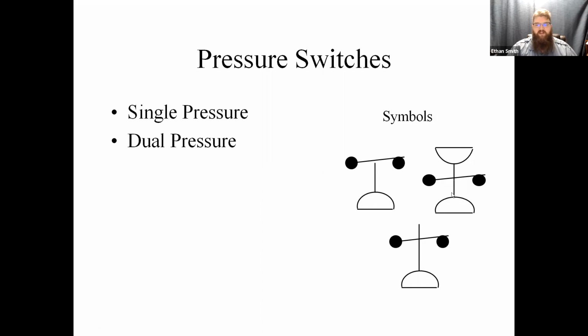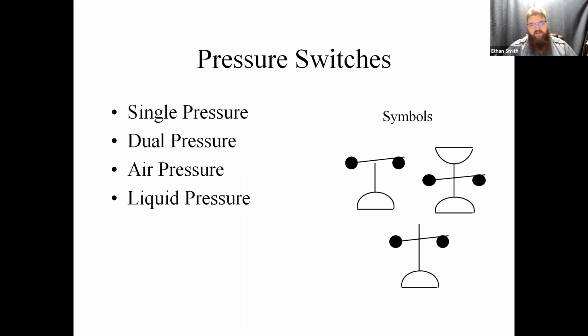We have dual pressure switches, which the symbol will have two diaphragms pictured on it, where we sense pressure from two different pressure zones and take the difference between them. And then we've also got manual reset pressure switches, which look like this. Usually they're single zone pressure switches, and then they've got a little stick that comes up on them on the wiring diagram. That indicates that it is a manual reset button on that. Okay. We use them for air pressure, liquid pressure, refrigerant pressure, all sorts of stuff. But in the end, they're switches, guys. They're open or closed. You can take voltage or resistance through them in any position.